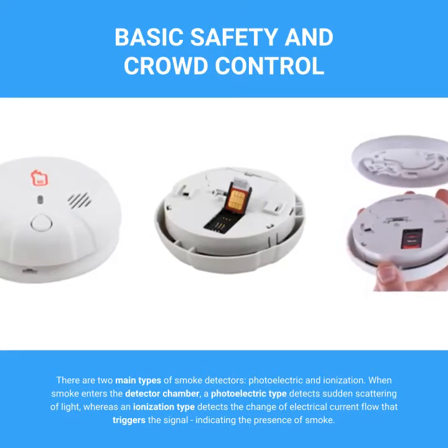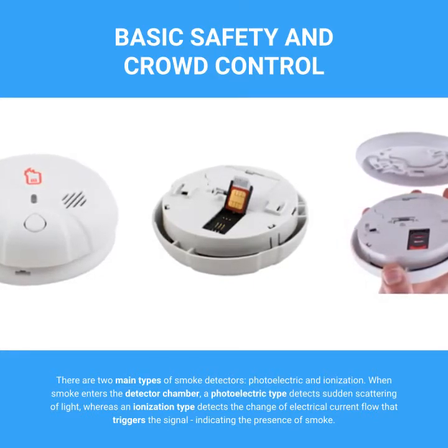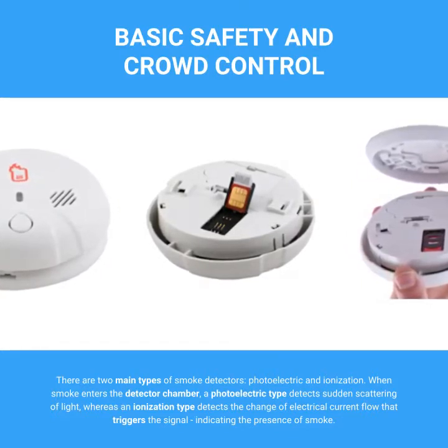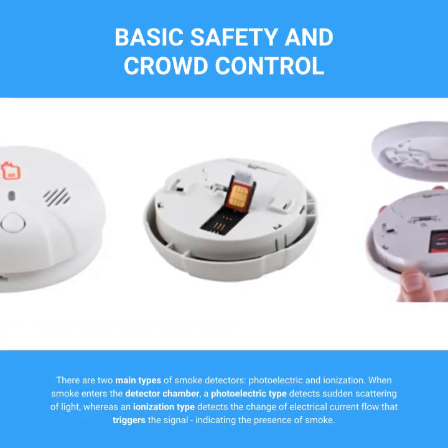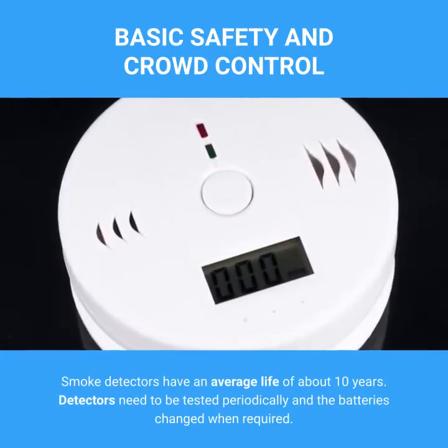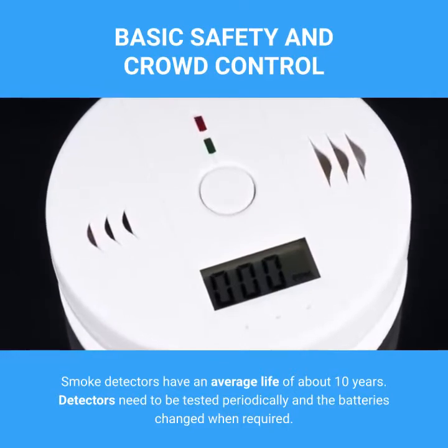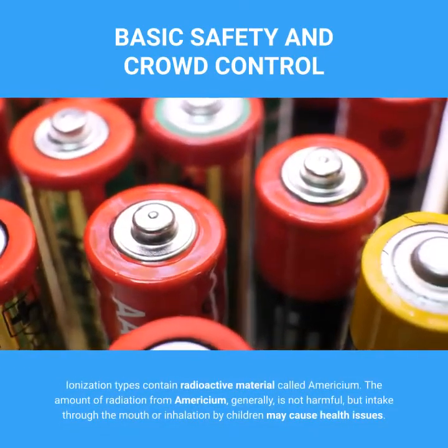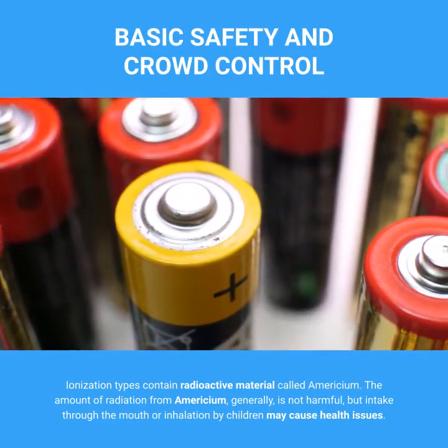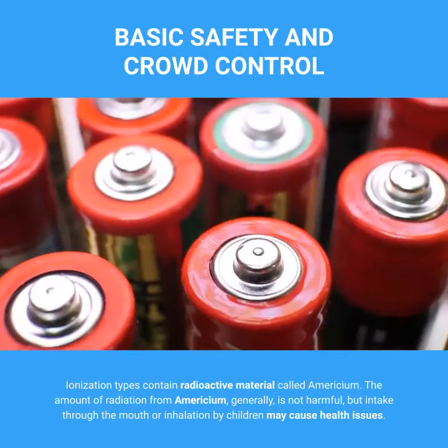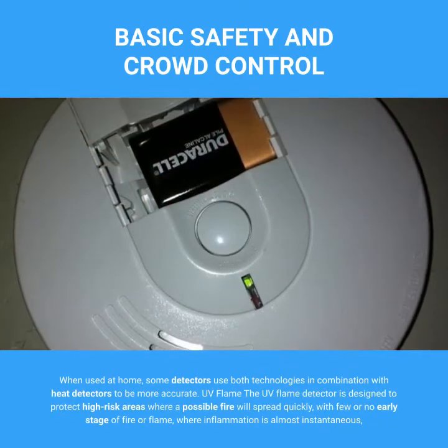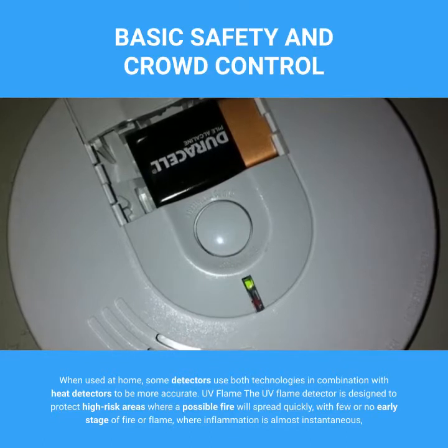When smoke enters the detector chamber, a photoelectric type detects sudden scattering of light, whereas an ionization type detects the change of electrical current flow that triggers the signal indicating the presence of smoke. Smoke detectors have an average life of about 10 years. Detectors need to be tested periodically and batteries changed when required. Ionization types contain radioactive material called americium; the amount of radiation is generally not harmful, but intake through the mouth or inhalation by children may cause health issues. When used at home, some detectors use both technologies in combination with heat detectors to be more accurate.